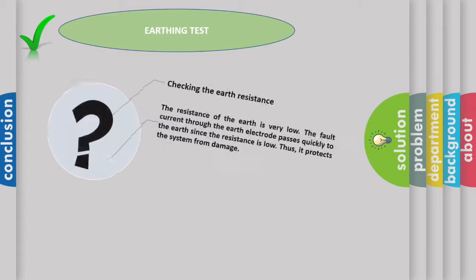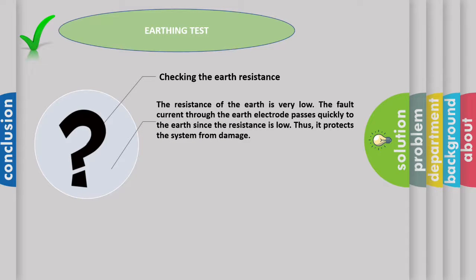Why we need to do an earth test? The test is actually to check the earth resistance. The resistance of the earth usually is very low. Basically, we follow the TNB specification, which is the resistance must be lower than 3 ohm. So, the fault current through the earth electrode passes quickly to the earth since the resistance is low. Thus, it protects the system from damage.